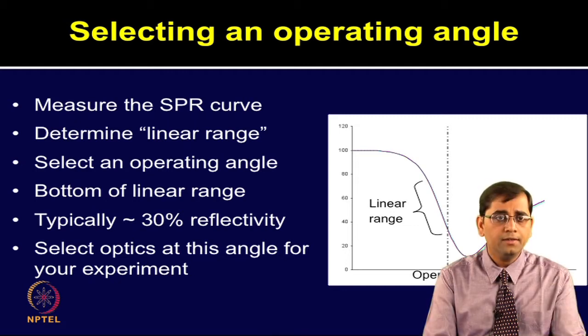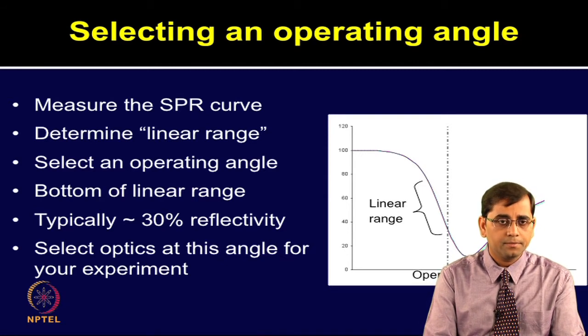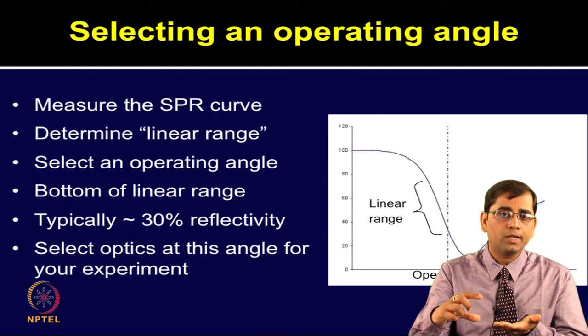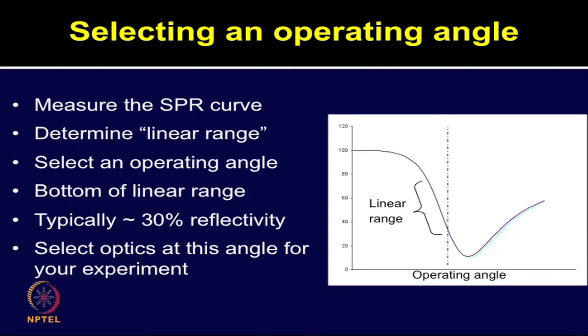In SPRi, the first and most crucial step is the selection of an operating angle. The SPRi device measures the SPR curve and determines the linear region. One needs to scan the whole optics through a range of angles and determine the linear range. A rough estimate is that typically around 30 percent reflectivity can be taken as the bottom part which represents the linear region. Select the optics at this angle for your entire experiment, so that all spots printed on the chip surface can be measured simultaneously.